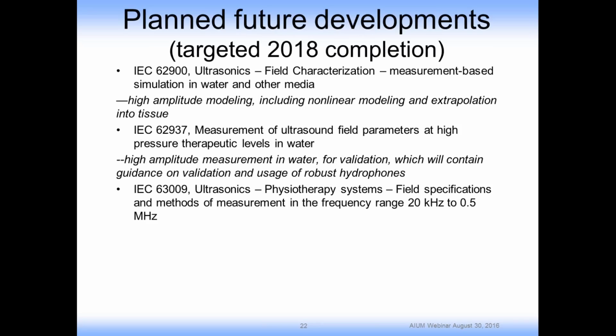I'll mention what's in the works in terms of IEC standards, all targeted for completion in 2018. First of all, this approach of doing mathematical modeling, including nonlinear modeling and extrapolating into tissue, is to be embodied in this IEC 62900 standard. The issue of how to work with robust hydrophones and make measurements at high pressures is being addressed in this 62937 standard that's underway. And finally, I will also mention that there is a standard that will extend the physiotherapy standards down to lower frequency, down to 20 kilohertz. And that is also underway.